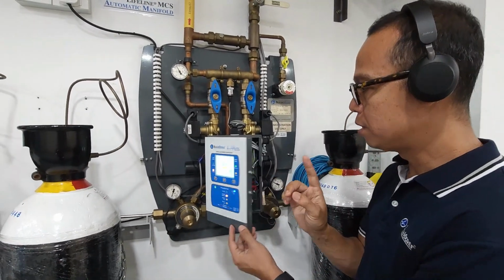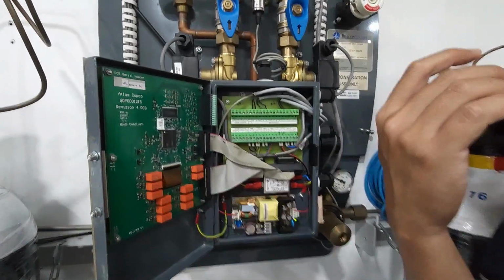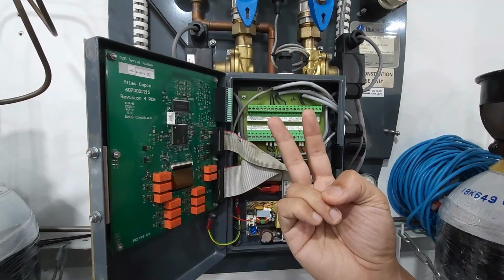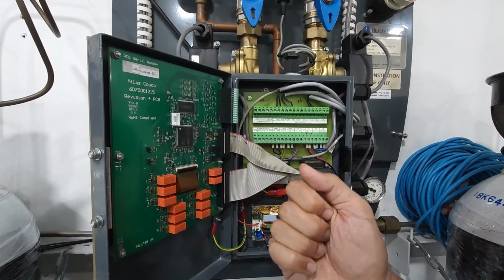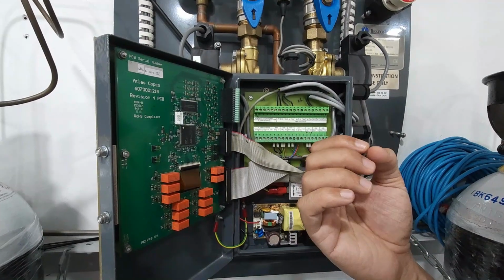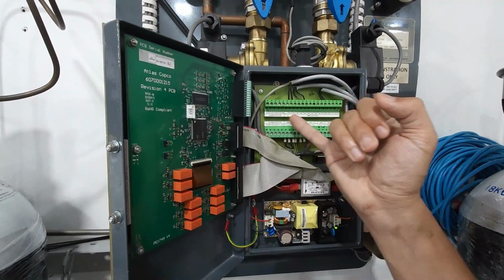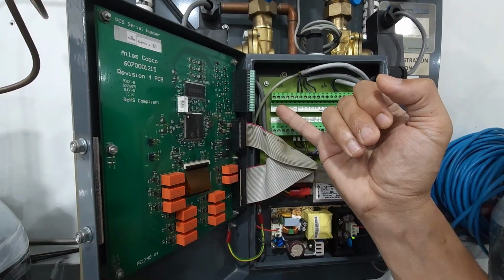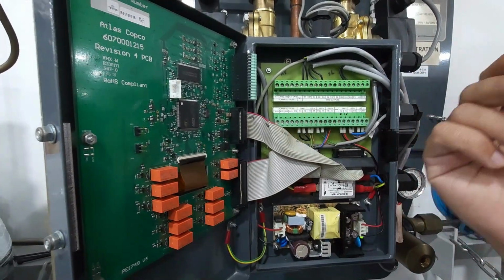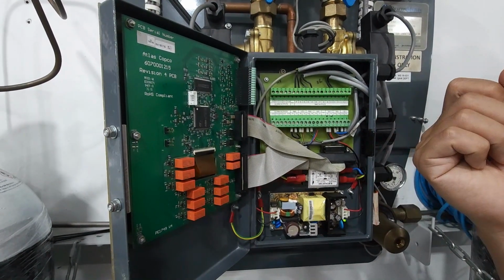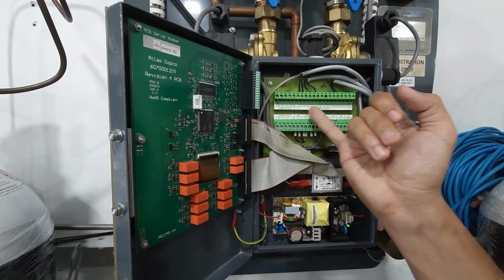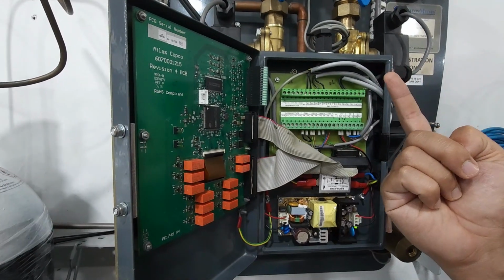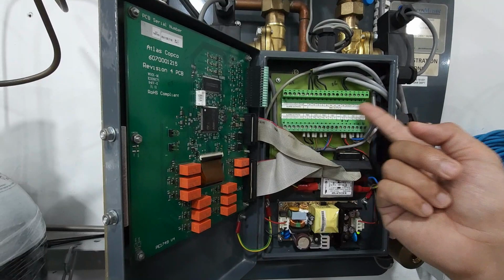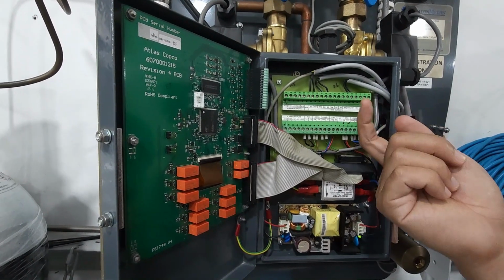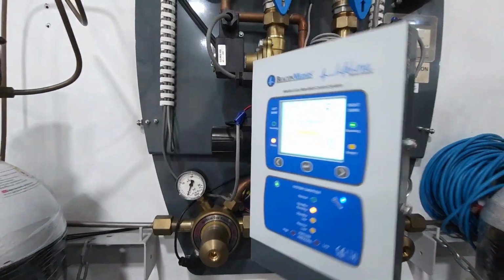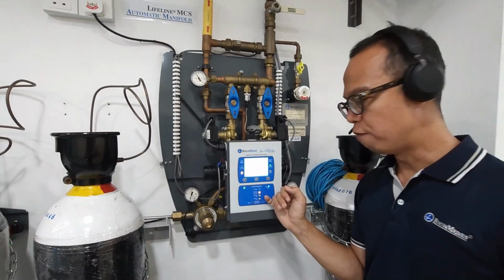Oh, by the way, one last thing that people usually ask about is alarm connections. There are two ways of doing it. If you're connecting to the BeaconMedaes MediPoint alarms, we use line contact monitoring alarms. So you would use the alarm outputs here, A10 to A14, or you can use it here. If you're not using the BeaconMedaes MediPoint alarms, you can connect using this BMS output. This BMS output uses two wires for one signal. Two wires for one signal. From B1 to A15, you can refer to the manual to ensure which one goes where for your change cylinder, standby running, standby low, and reserve low.